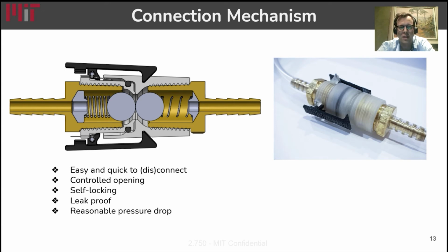It also makes the connection self-locking in case of an accidental disconnection. The black clips keep the system connected during use, and we mitigated the risk of leakage by adding an O-ring in the catheter connection and by having a long threaded connection between the case and the barbed fitting. The minor loss coefficient through the connection was estimated and deemed reasonable.